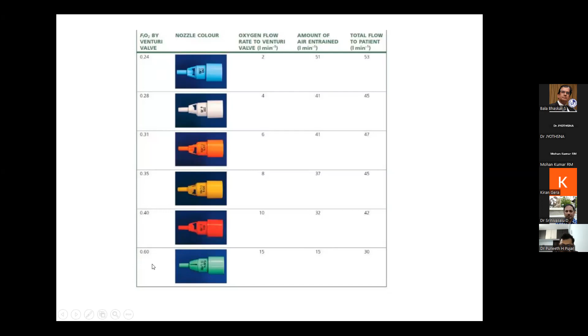So when 51 liters means more air is being diluted, so less FiO2 is being delivered to the patient. Here the amount of air being diluted is very less, so the FiO2 delivered to the patient will be more. So how do you calculate the device flow rate? With the help of the air oxygen ratio, we can calculate the device flow rate.